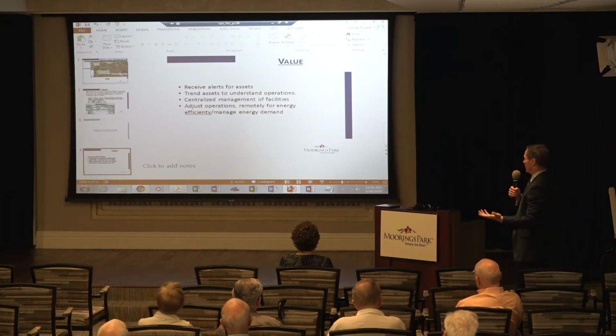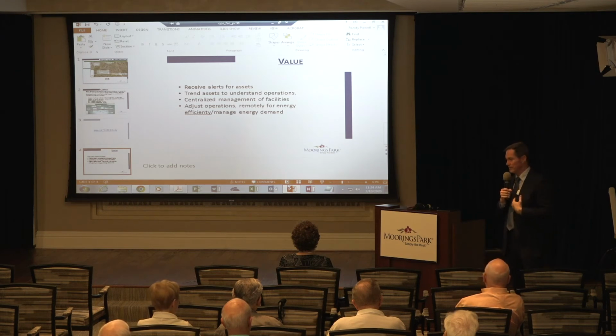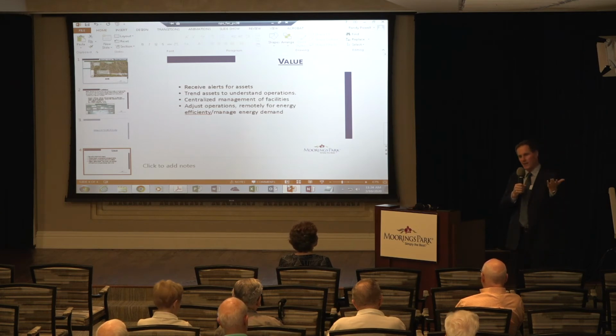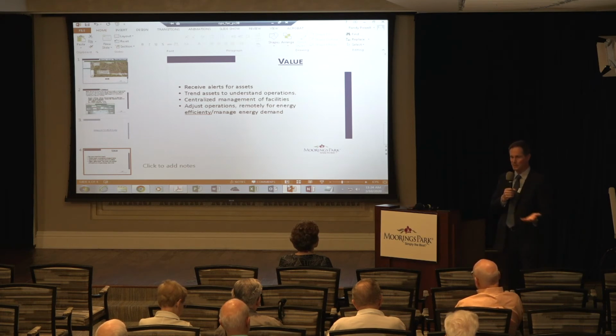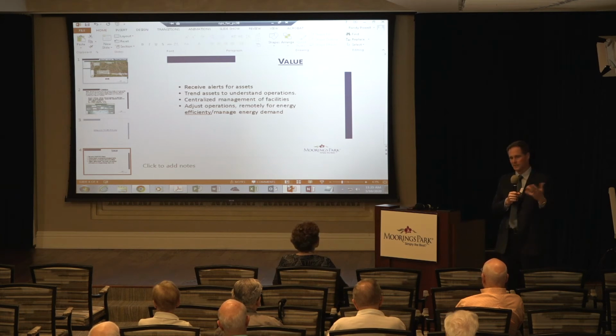And then ultimately adjusting operations remotely for energy efficiency and managing that demand. I use the Trio as a great example, but the building I work in, no one's typically in there Saturday and Sunday except Edwin and I. We could run that building at 76 degrees Saturday and Sunday, and then start bringing it down Monday morning back to, say, 74. Same with the south end of Orchid Terrace, where home health is, there's no need maybe to cool that. We'd have to do some math and calculations to really understand if that's most efficient, but there are opportunities to drive efficiencies by being able to capture this sort of data and manage it electronically.